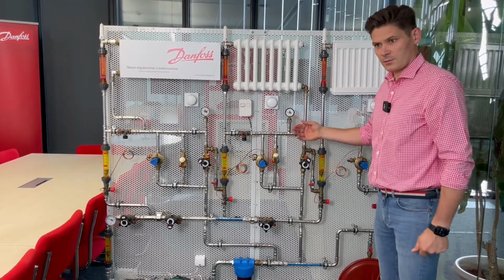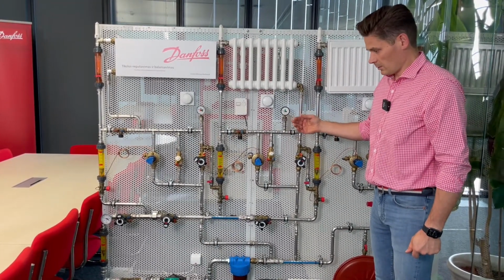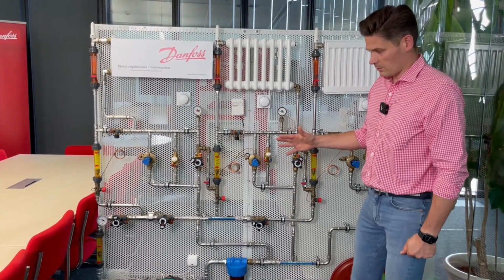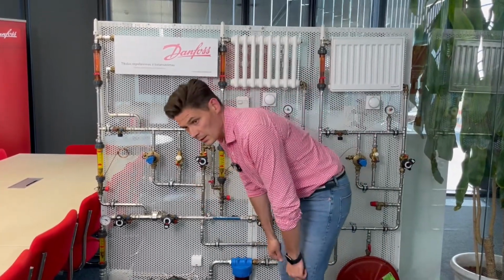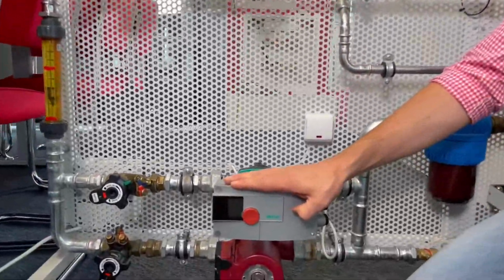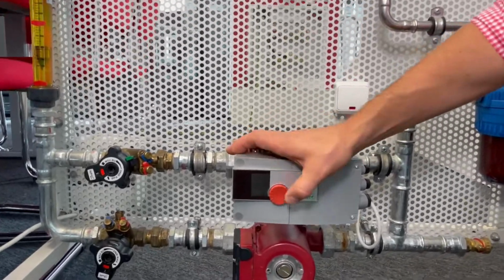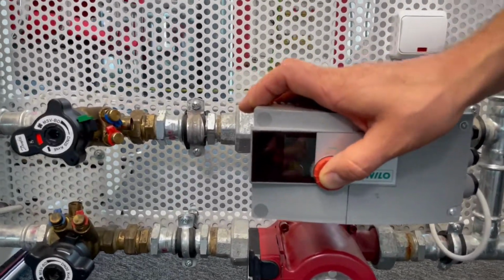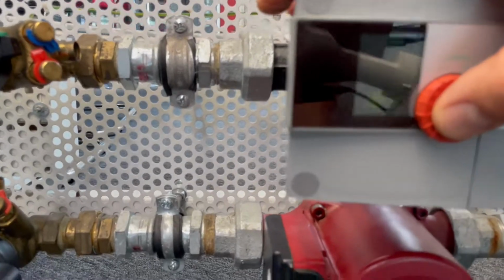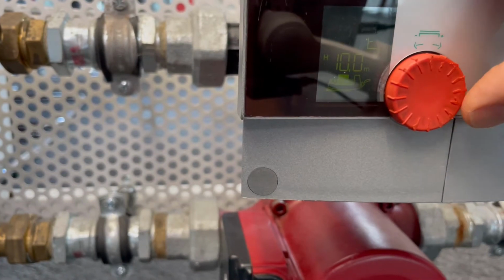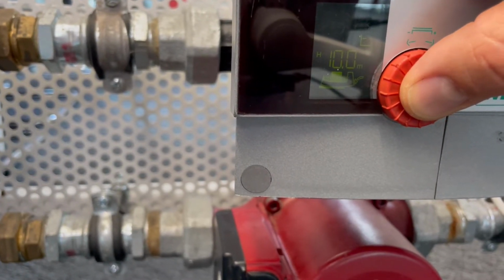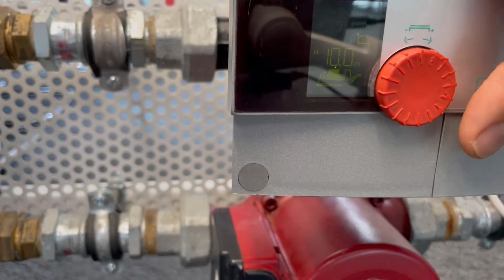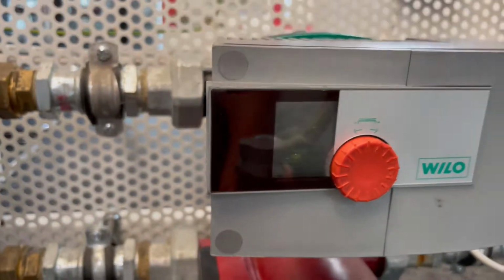While commissioning manual balancing valves, we always advise to set the pump head at maximum speed and to set it at constant pressure. So I don't want the circulation pump to play with flow when I do commissioning with manual balancing valves. After we did commissioning, we always need to make pump optimization, and I will show how to do it. Okay, so maximum speed, delta PC, constant pressure.